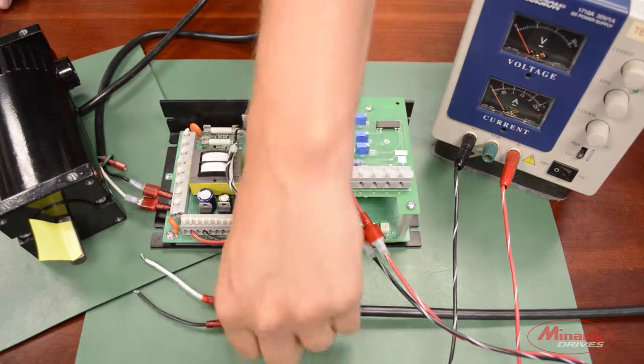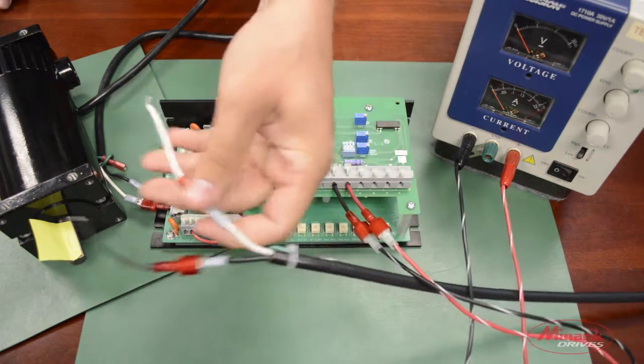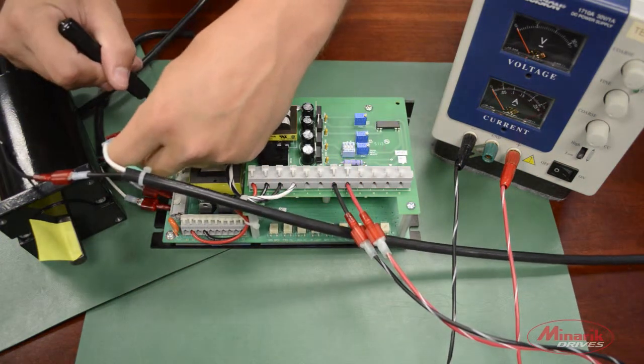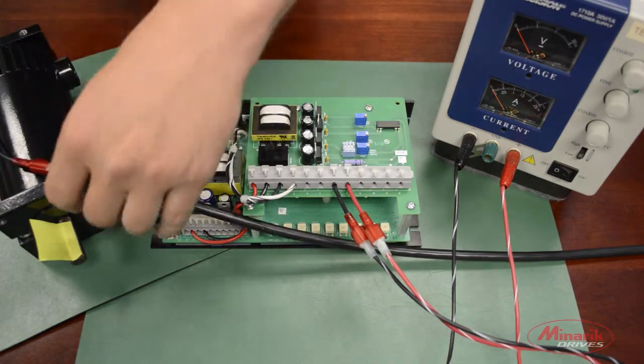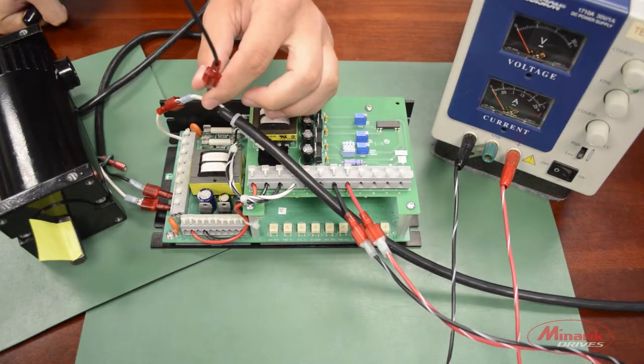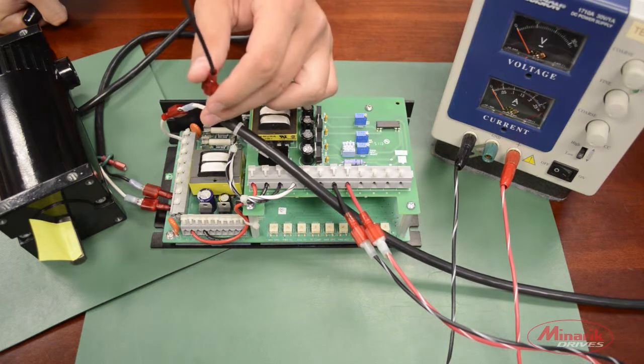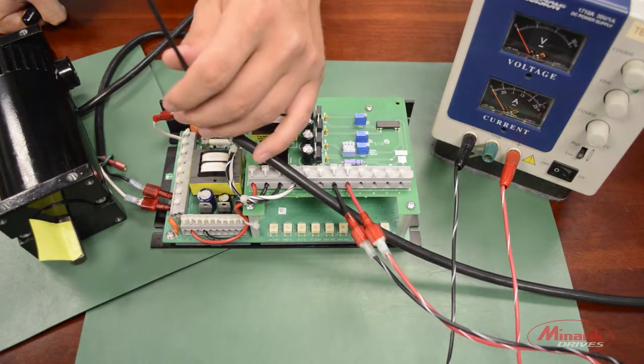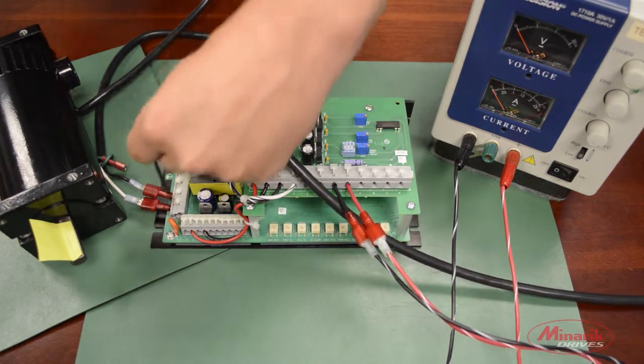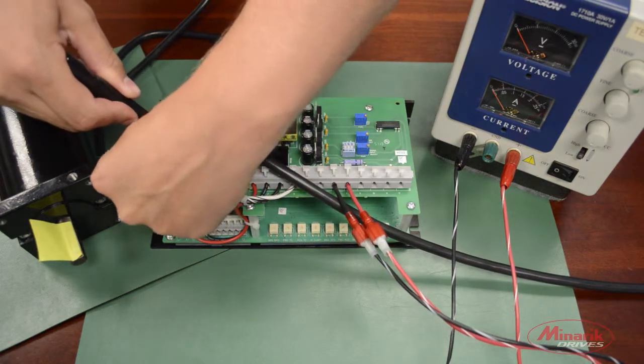Now we will connect our power leads to L1 and L2. We'll take the hot lead, connect it to L1, and then neutral to L2. L2 has two spots, one for 230 volts AC and one for 115. For this demonstration, we'll be using 115 volts AC.